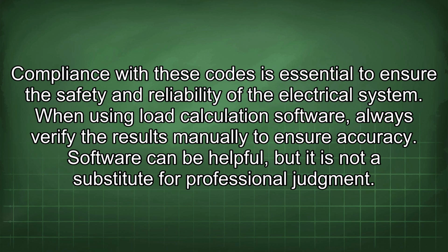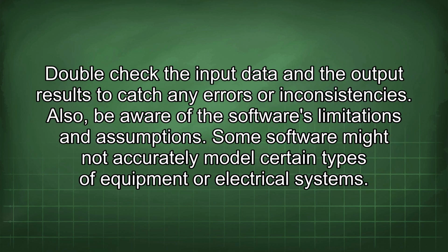When using load calculation software, always verify the results manually to ensure accuracy. Software can be helpful, but it is not a substitute for professional judgment. Double-check the input data and the output results to catch any errors or inconsistencies. Also, be aware of the software's limitations and assumptions. Some software might not accurately model certain types of equipment or electrical systems.